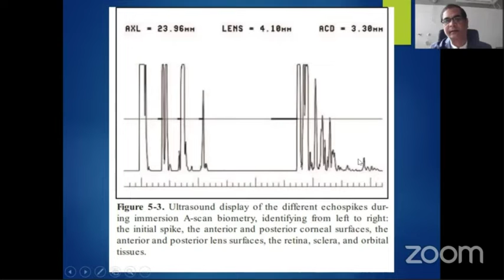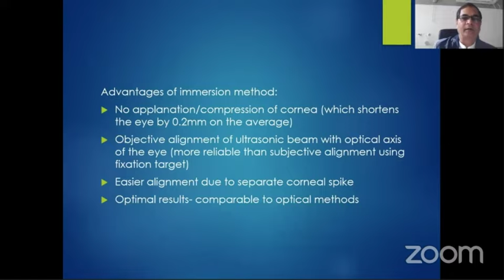The advantage of immersion method is no applanation or compression of the cornea, which shortens the eyeball by 0.2 millimeter on an average. Many studies have shown that. The objective alignment of the ultrasonic beam with the optical axis of the eye is more reliable than the subjective alignment using the fixation target. Easier alignment due to separate corneal spikes, and optimal results comparable to the optical method.